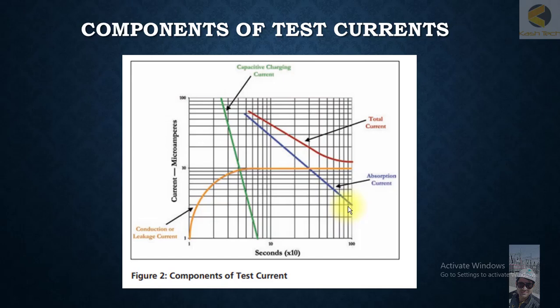This is the capacitive charging current. After five time constants, it's approaching a very low value, almost near to zero. You can see when the leakage current at the start is high, the reading of megaohms is low.